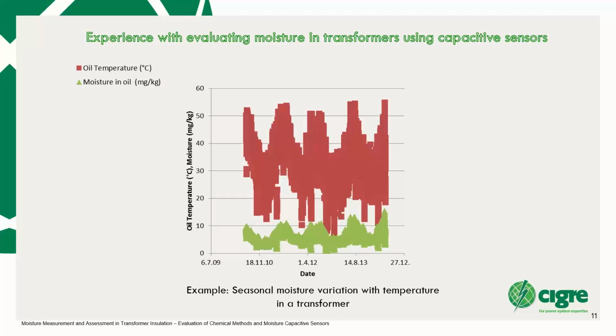But we can see it very, very well when we have capacitive sensors. We can see the temperature variation, which is seasonal, and together with that, also the variation of moisture. Especially, this is very good to be seen in transformers with a certain cooling mode. For example, ON mode will, of course, be better to represent this seasonal variation than direct mode of cooling.